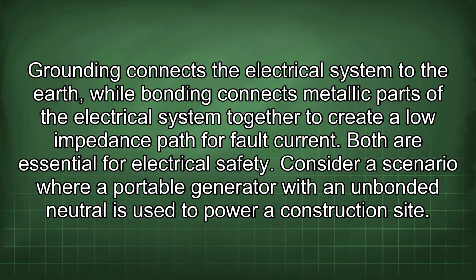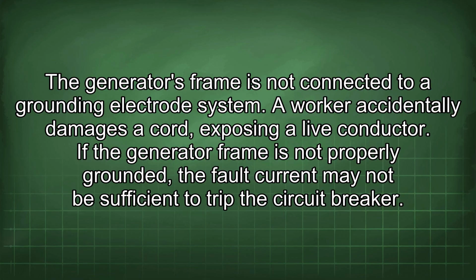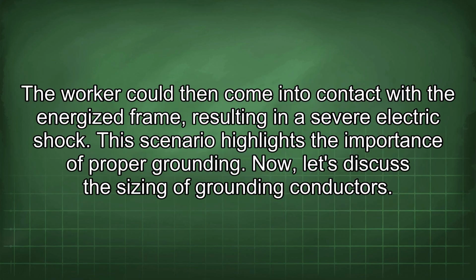Consider a scenario where a portable generator with an unbonded neutral is used to power a construction site. The generator's frame is not connected to a grounding electrode system. A worker accidentally damages a cord, exposing a live conductor. If the generator frame is not properly grounded, the fault current may not be sufficient to trip the circuit breaker. The worker could then come into contact with the energized frame, resulting in a severe electric shock. This scenario highlights the importance of proper grounding.